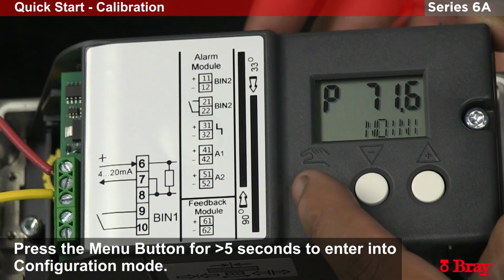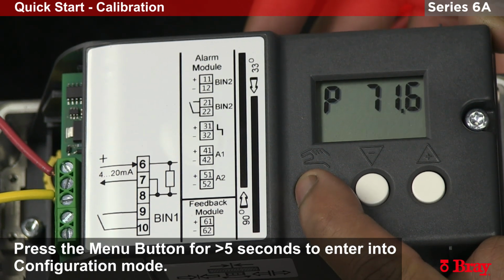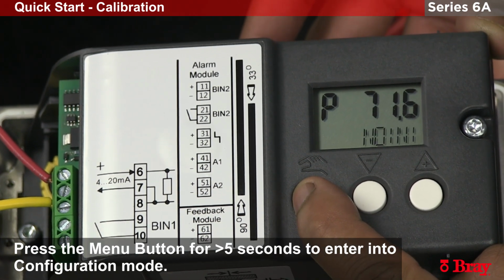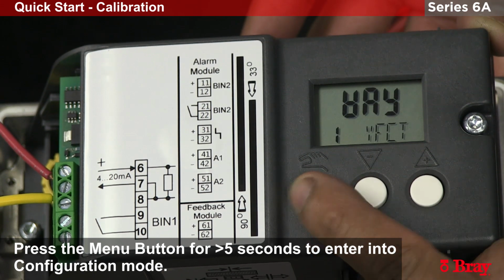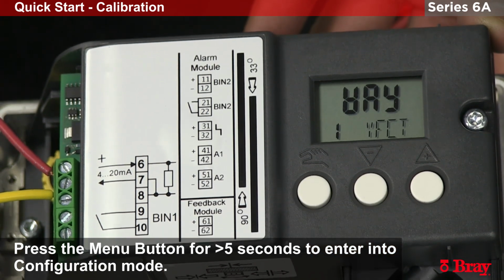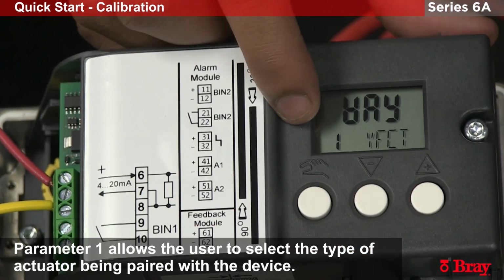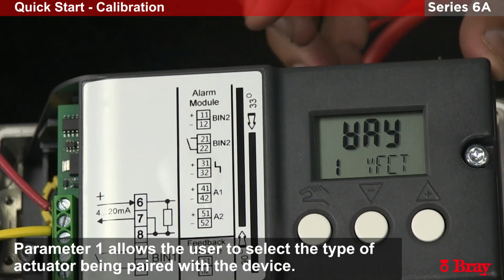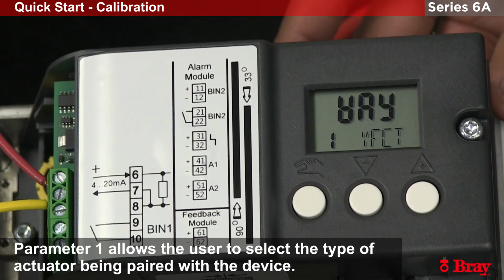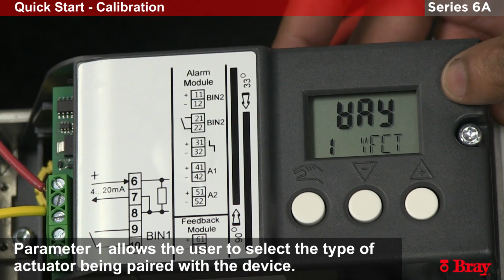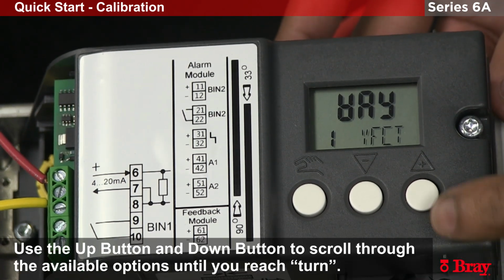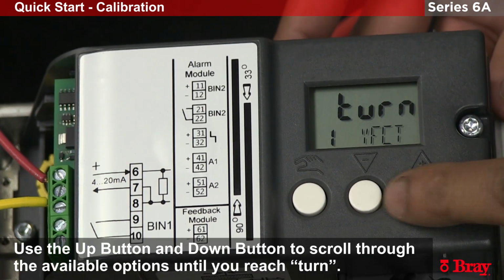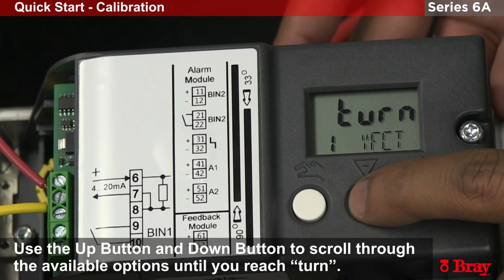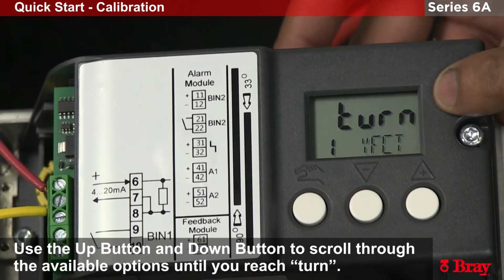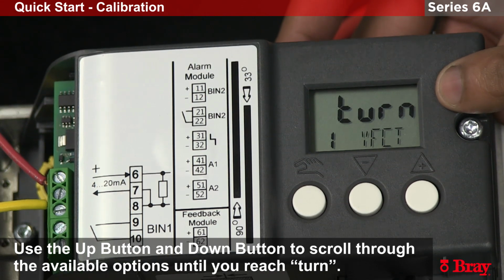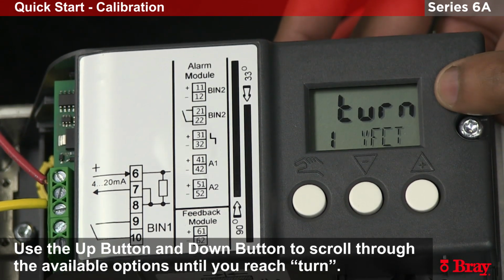To go into calibration, we're going to hold down the hand button for 5 seconds, and the window will switch to the setup section. We're in window number 1, as stated in the bottom left corner. This is where we're going to tell what kind of actuator we're mounted onto. At the moment it's saying way, which is for a linear actuator. We will use the up and minus buttons to switch through this window to get to the turn section. This is to state that we're on a rotary actuator.